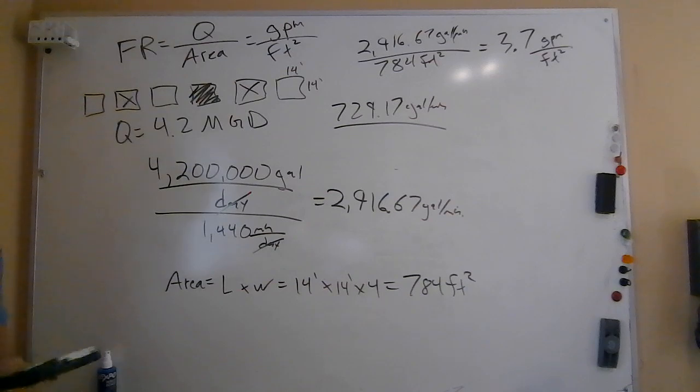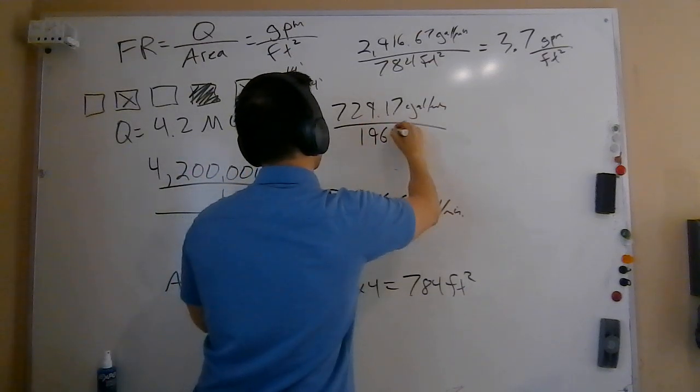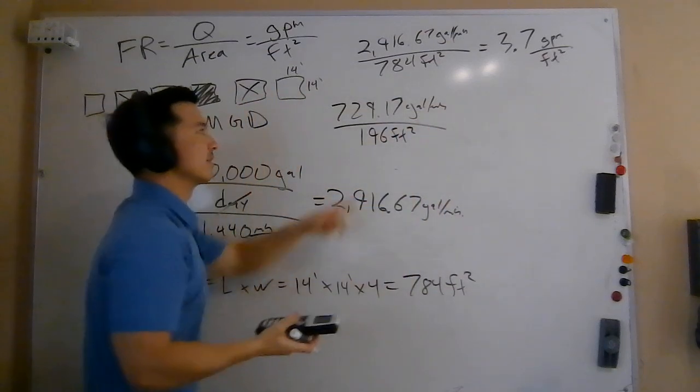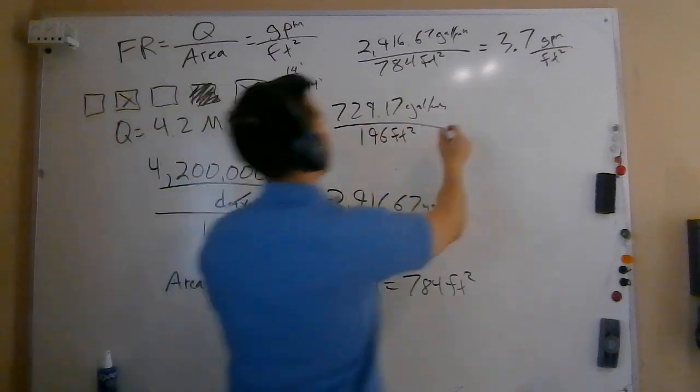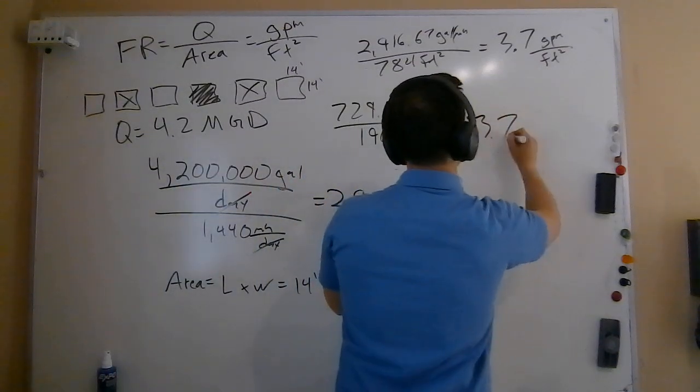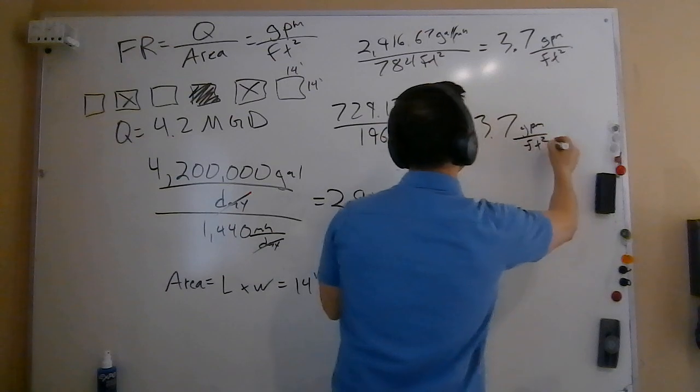So 14 times 14 is going to give me 196. So 196 square feet, that's the area of one filter. When I divide these out, I should get the same exact number. So let's figure that 196. And I get to 3.7. And that's again in gallons per minute per square foot.